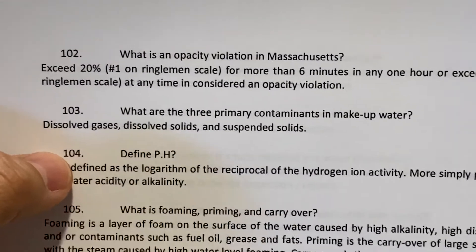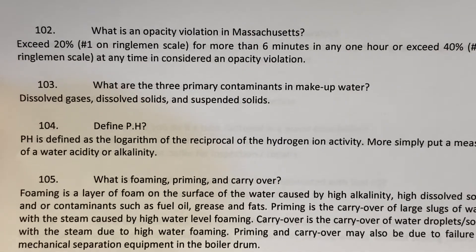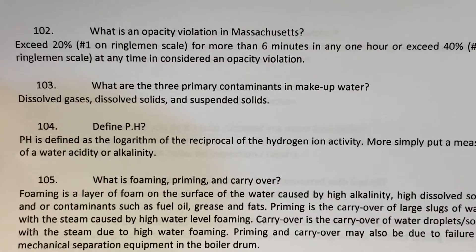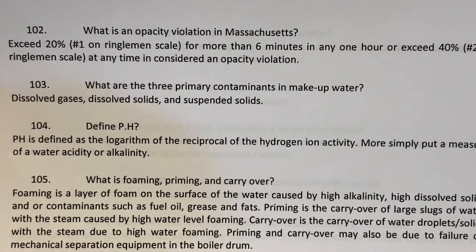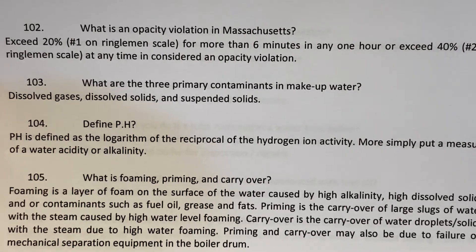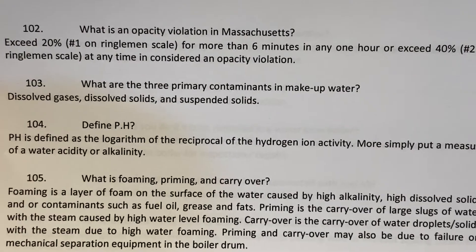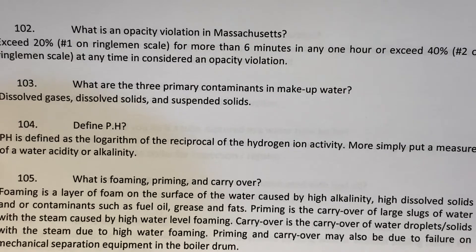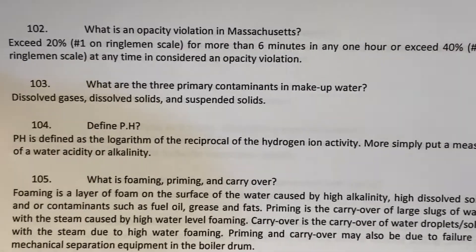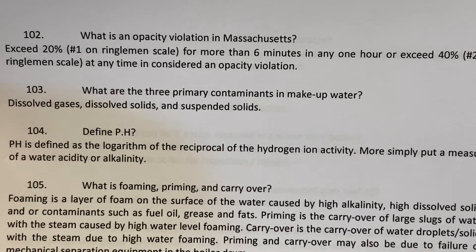What is an opacity violation in Massachusetts? Exceeding 20% — number one on the Ringelmann scale — for more than six minutes in any one hour is one opacity violation. Exceeding 40% — number two on the Ringelmann scale — at any time is also considered an opacity violation.